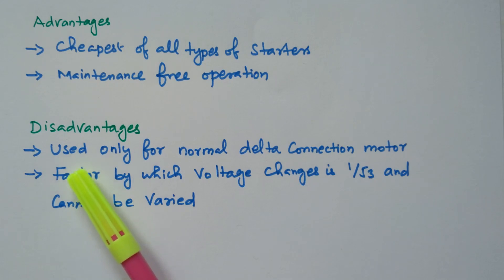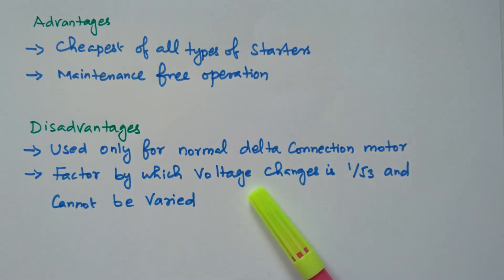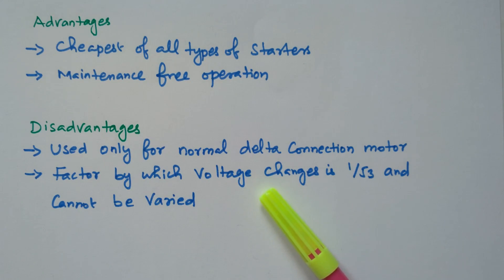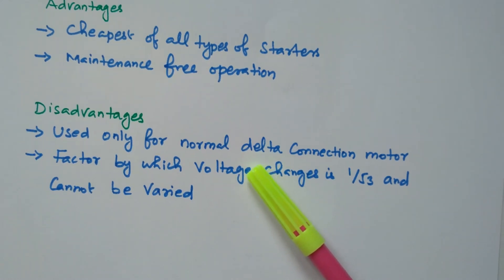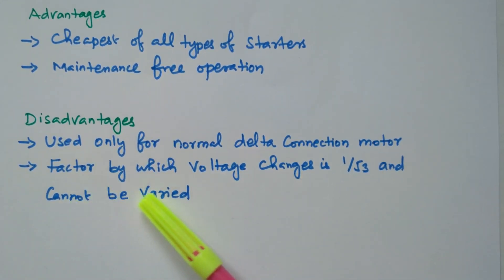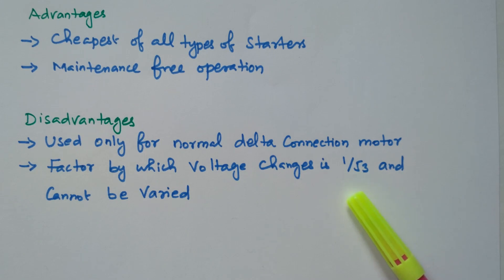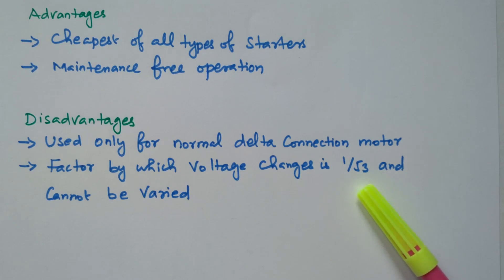Now the disadvantages: it is used only for normal delta connection motors. If the stator winding is connected in delta, then only we can use this starter, because the stator winding is initially connected in star and finally in delta. So we need a delta-connected motor. Also, the factor by which the voltage is changed is fixed at 1 by root 3 — we are applying only 1 by root 3 of the voltage at the beginning, and it cannot be varied. We cannot change it to a lower or higher value; it is always 1 by root 3 times the rated voltage.